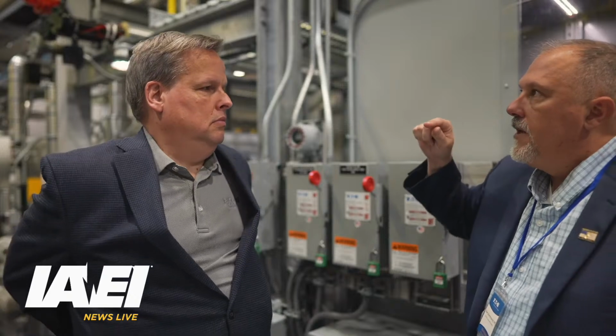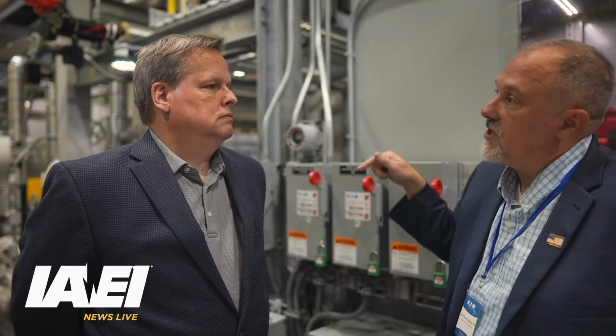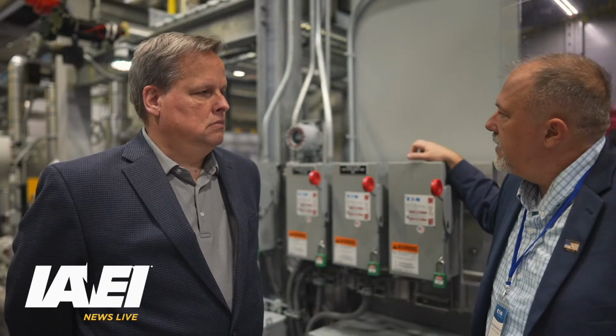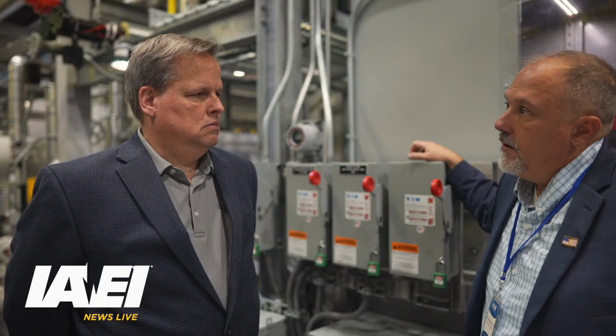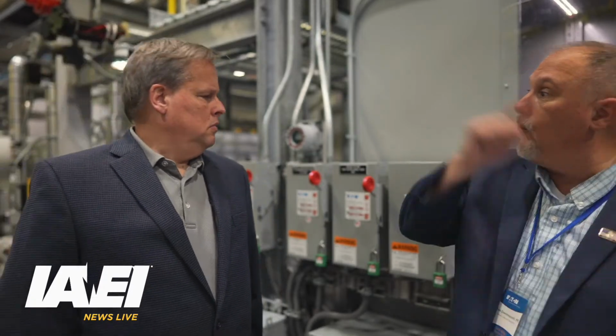The other thing is, my conductors passing through the calculated space can't exceed 40%. And there was another one in there too. I can't remember, but they give you rules. Let me click on it. There it is. The total of all conductors installed in any cross section of the wiring space does not exceed 40% of the cross sectional area of that space. The total area of all conductors, splices, and taps installed at any cross section of the wiring space does not exceed 75%. And then the bending space: in general I have to have proper bending space, but for a 4 and larger it has to comply with 314.28(A)(2), and there has to be a warning label that says there are other conductors from other sources in here, and it has to tell you where to do the disconnect.